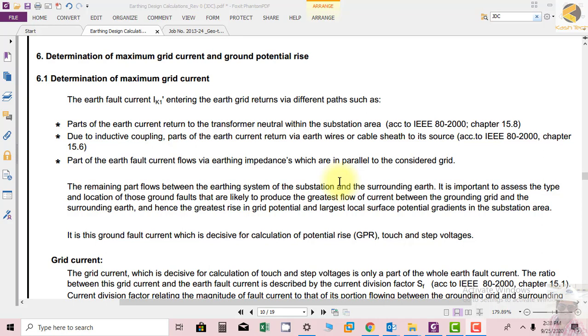Part of the earth fault current flows via earth impedances that are in parallel with the grounding grid. This could include nearby towers, pipes for watering or firefighting systems going through the ground, and building foundations — all of which act as return paths. The remaining part flows through the earthing system of the substation and surrounding earth.